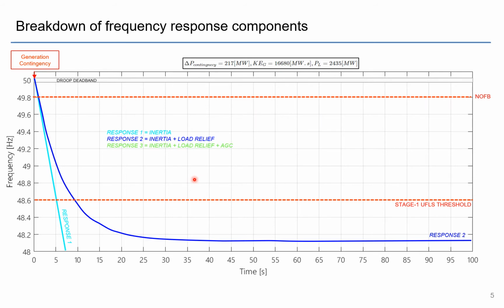If we had load relief and just the AGC system, so this is just the automatic generation control, like a central control pinging active power outputs to different generators, then we'll get an improvement in frequency response. But you see here that it's still breaching the upper threshold because AGC is slow. It takes quite a few seconds to send a signal from the central operating center to the different units in the field.